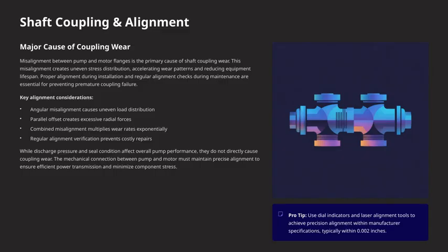Let's talk about shaft coupling and alignment, a major factor in equipment longevity. One of the primary causes of coupling wear is misalignment between the pump and motor flanges. When these components aren't properly aligned, it creates uneven stress distribution across the coupling. This uneven stress accelerates wear patterns and can significantly shorten the lifespan of your equipment. To prevent this, proper alignment during installation is crucial, and regular checks during maintenance are just as important.